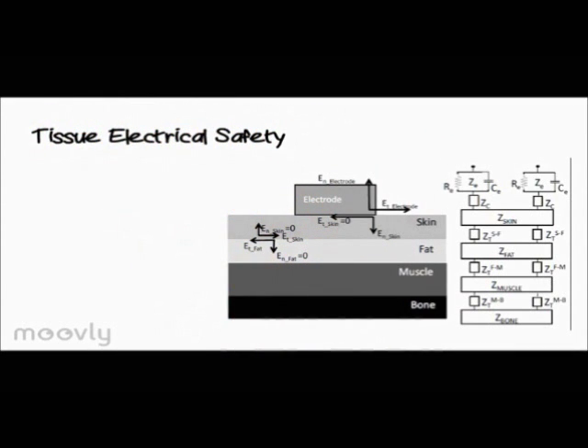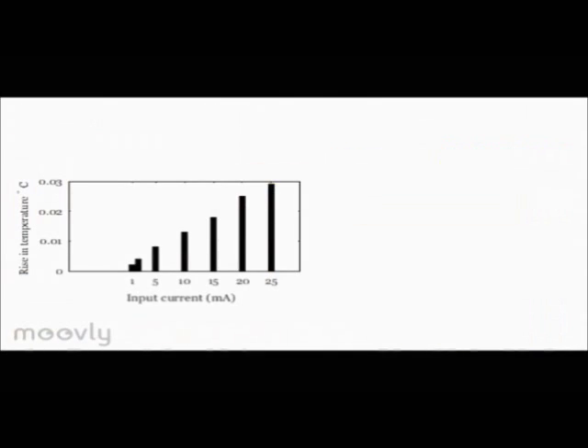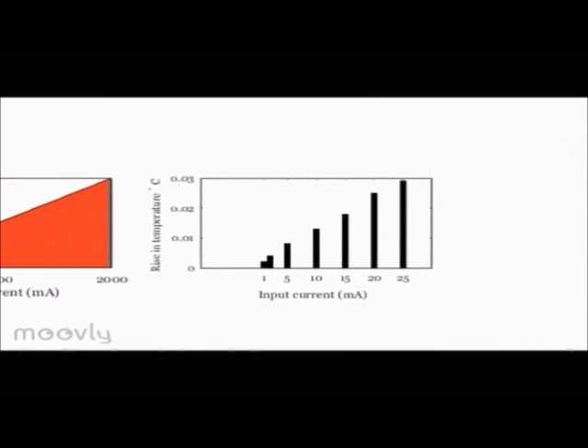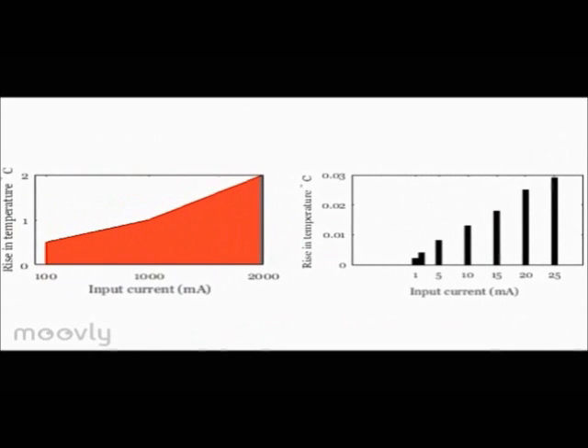For thermal safety, we use the partial differential equation based and empirically evaluated thermal distributions. We witnessed that the maximum rise in tissue temperature due to signal propagation is very minimal compared to the heat generated from radio frequency signals.